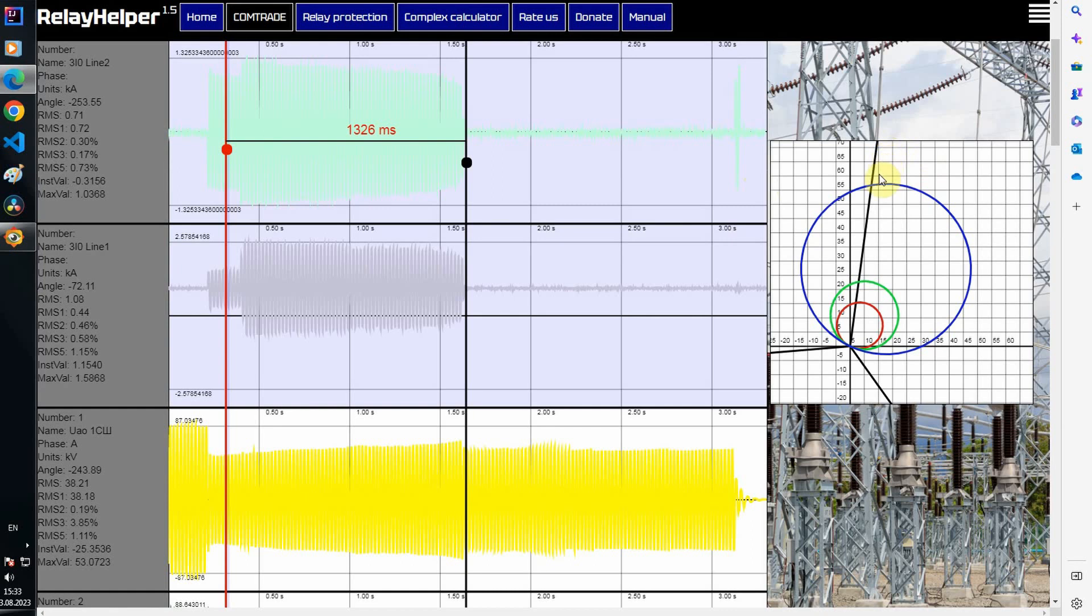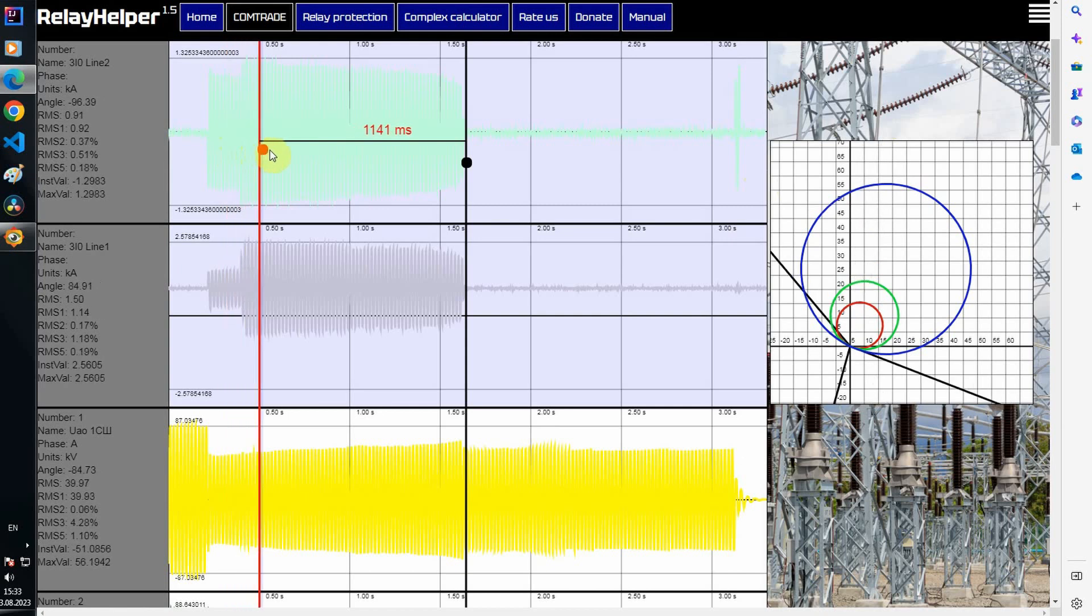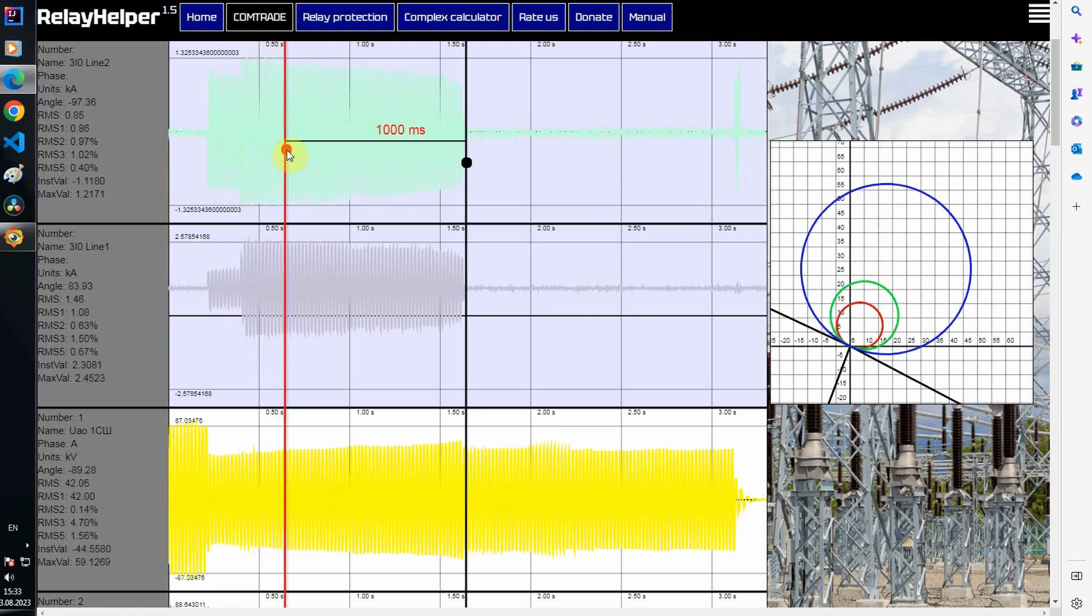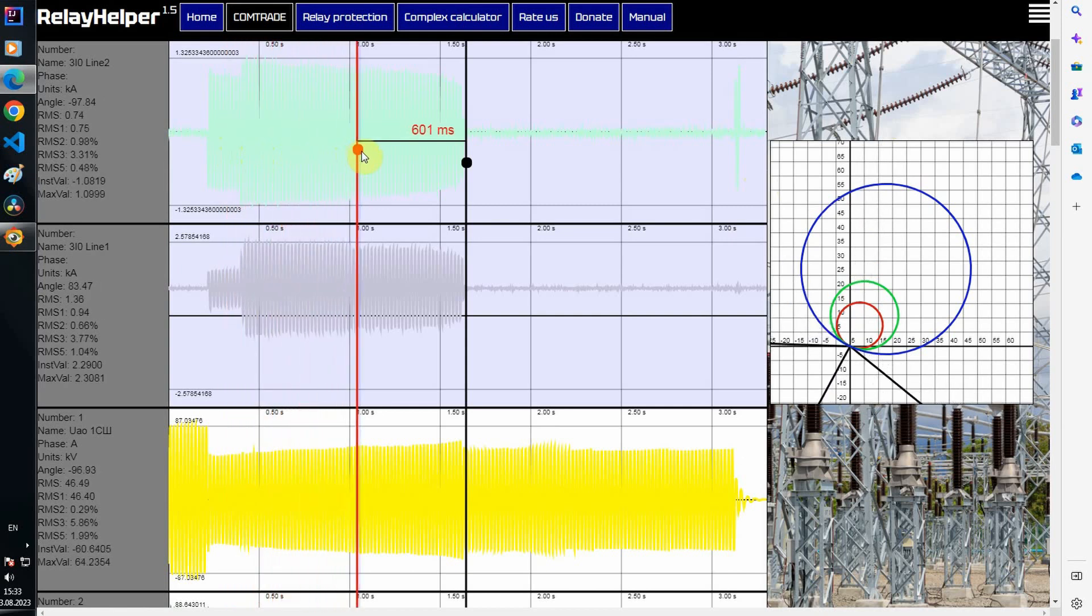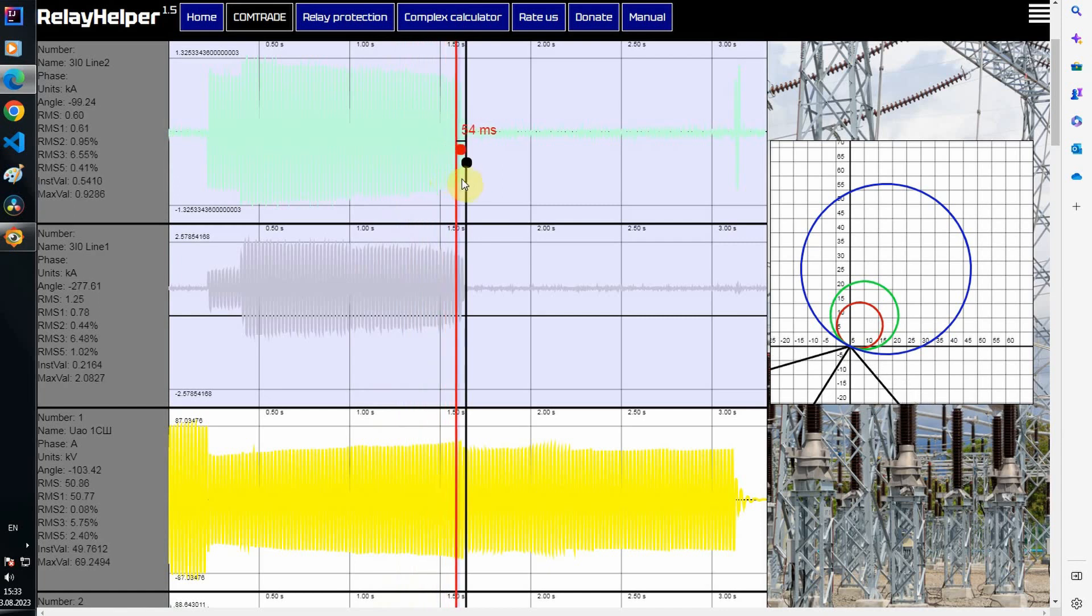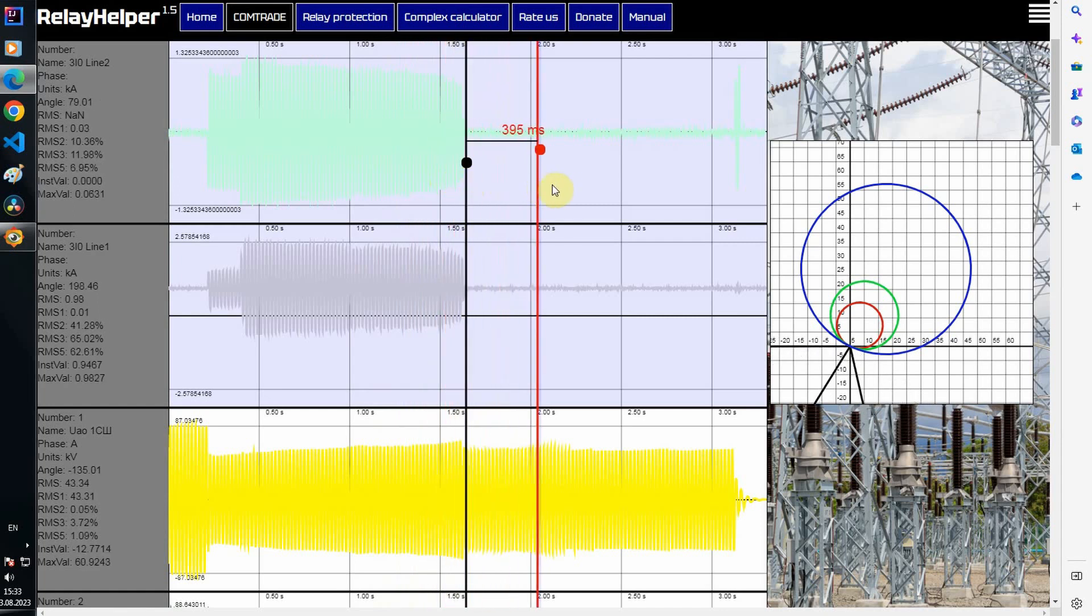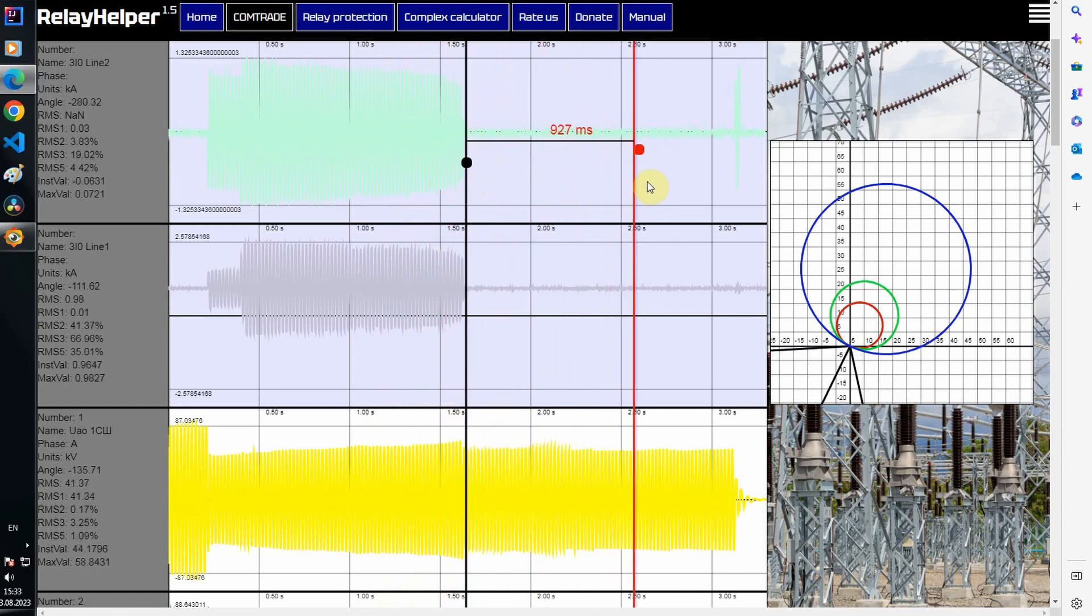From the second section until the end of the fault, power is transmitted along the line towards the substation from which we received the comtrade file.